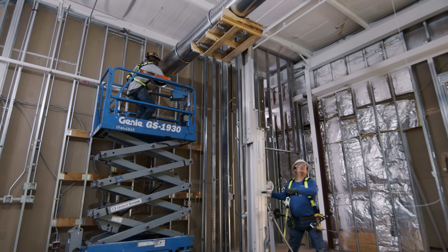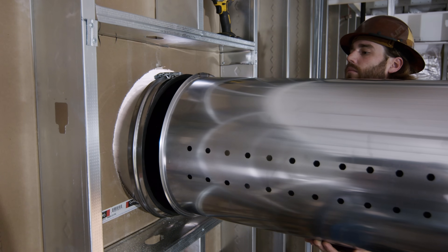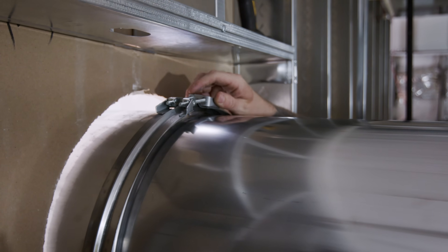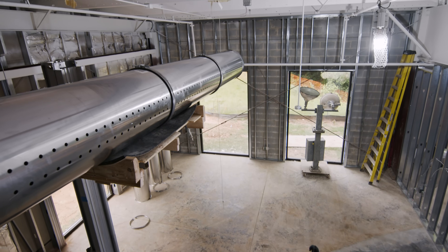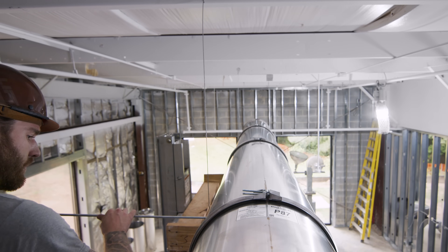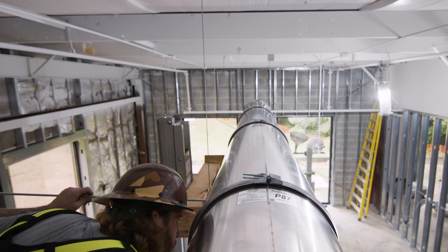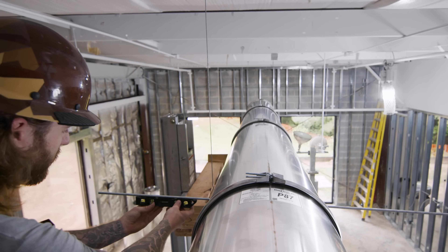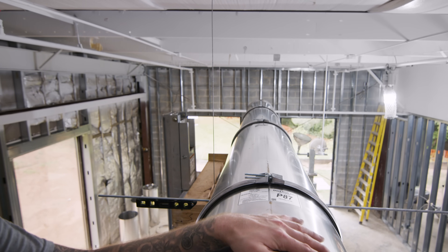Right now we're trying to line up the duct work with the existing duct work through the wall so we can go ahead and make the connection. We have our big clamp there already, so it's a whole lot easier. We're putting these diffusers on level — the way we do it is we use a threaded rod, put it all the way through, and then put a torpedo level on one side to check if it's level or needs to be adjusted.